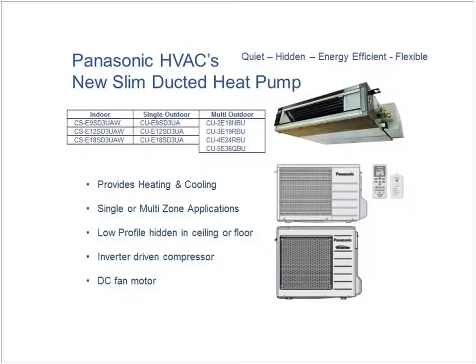So this is an ECM motor, so this will cycle up and down based on temperature and what's coming into the inside air. So if I put an ERV or an HRV, which is attached to a fresh air system, and I drive that air through there, I never see enough delta. So one of the caveats about this is it will only accommodate about a 30-degree delta. So if I want 70 degrees out, I have to have 40 degree better air coming in, which with an ERV, I'll never see a 30 degree delta, or an HRV, I'll never see a 30 degree delta.